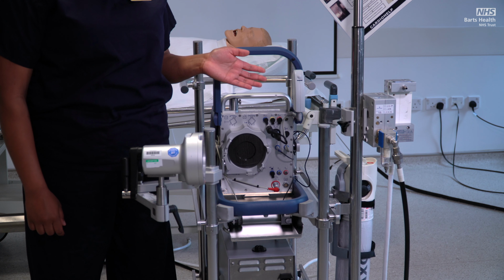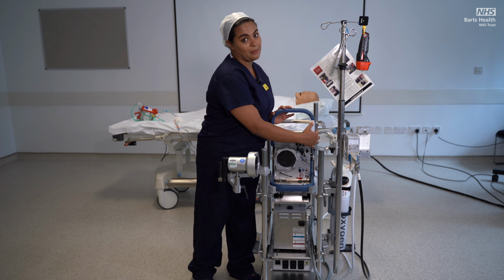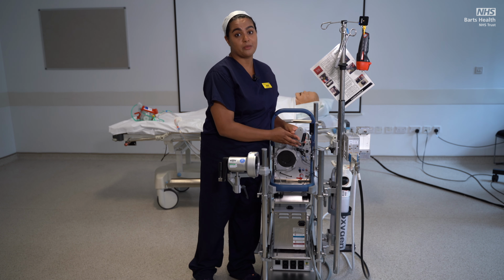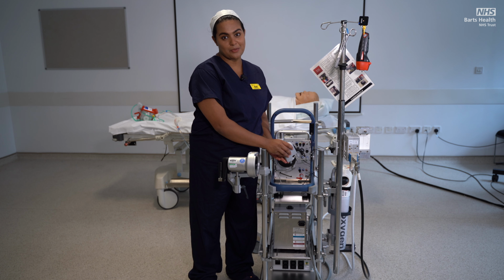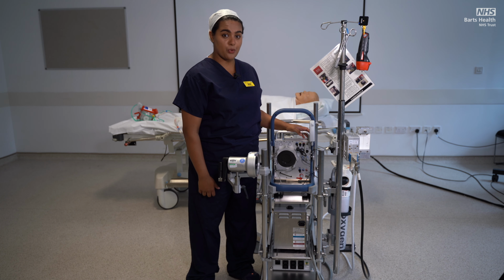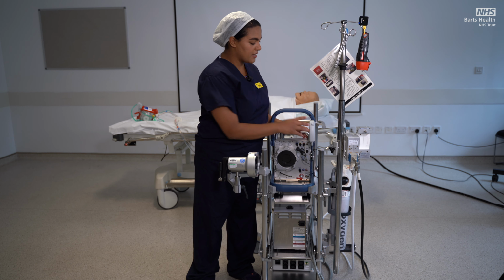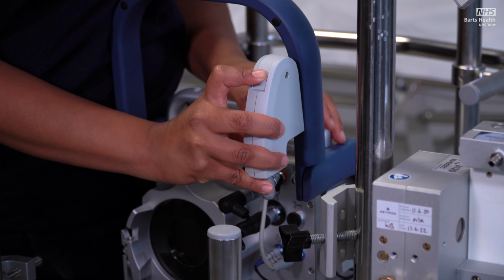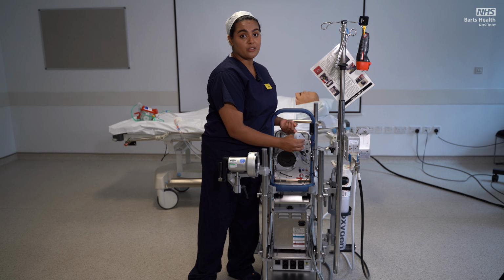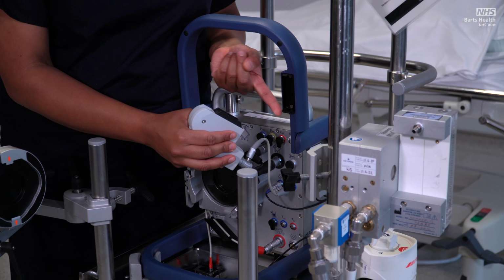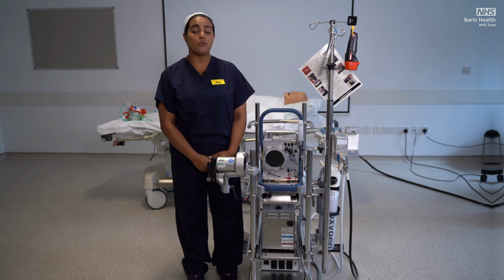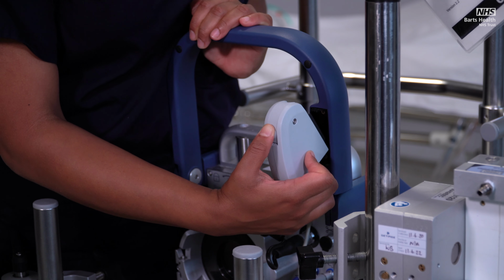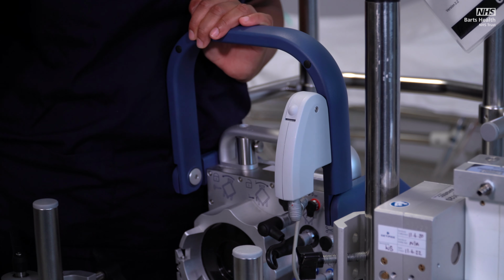This is the handheld venous probe. It measures the blood parameters of the patient by non-invasive optical sensors. The venous probe is attached to the drainage tubing during the ECMO run, and it measures the SvO2, hematocrit, HB, and venous temperatures. When removing the venous probe away from any attachment, always press down on the release button found on the probe head. Then remove the lug away from the tab of the correlating housing. When not in use, the venous probe should be rehoused in the measuring cell of the blue safety bar.